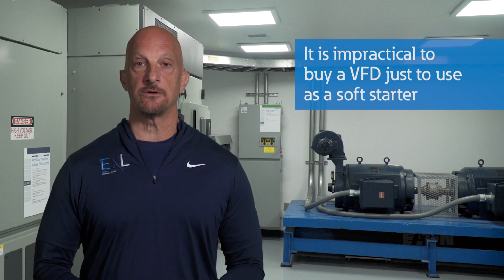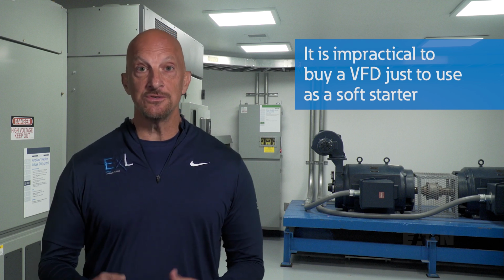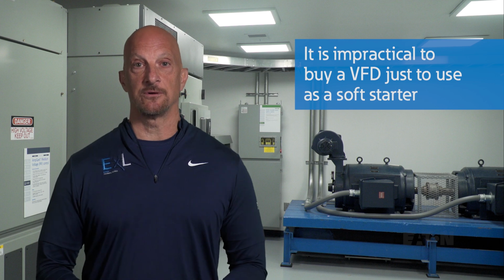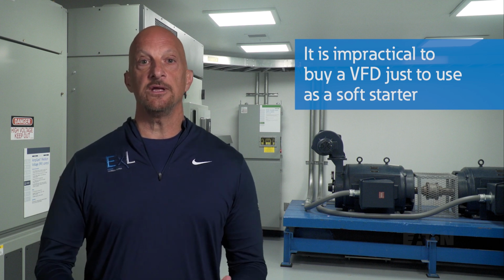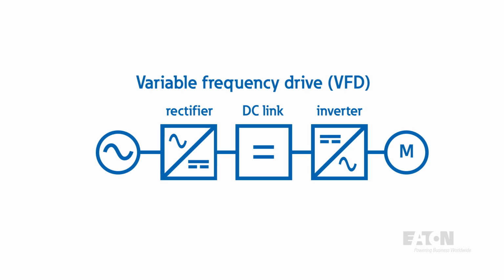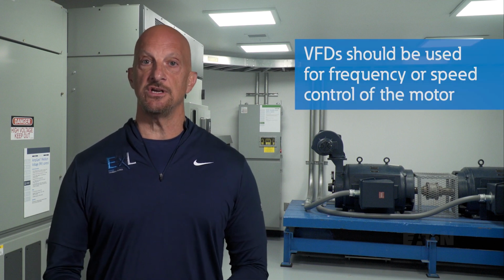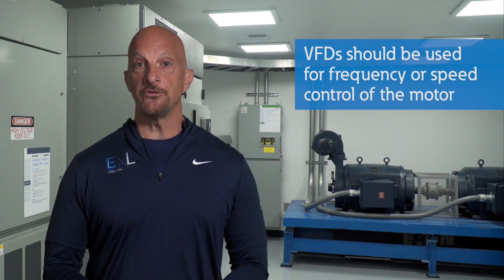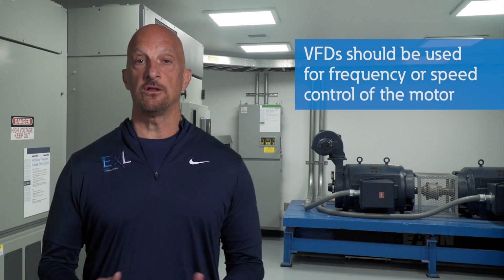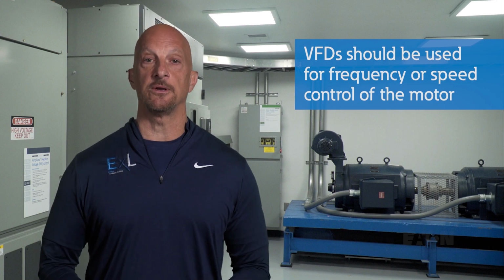Now, one thing that's extremely important to understand is that you would never buy a VFD and use it only as a soft starter. I'll repeat that. Don't use a VFD only as a soft starter. Why? Well, don't forget that a variable frequency drive converts the frequency by first taking the AC input and converting to DC with a rectifier, and then it converts it back to AC with an inverter. These two converters have losses, which means that if you operate at 60 Hz, you would pay for those losses all day, every day. But if you're using a VFD as intended to change the frequency or speed of the motor, you will see all the benefits that we mentioned previously, including energy savings, speed control, and soft starting.